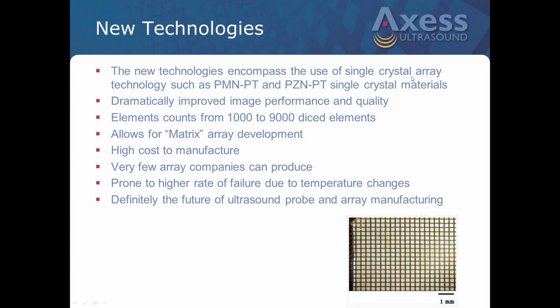Single crystal arrays are truly that. It's an absolute single piece. Think of it as a single piece of glass, crystal material, that's all one. And essentially the entire array is firing. I'll get into this a little bit more, but there's a lot of electronic control over single crystal arrays. What it means is a single crystal versus individual elements. Now, one of the things single crystal does, and I am a firm believer, and I've seen many images with various manufacturers' probes, is a dramatic improvement in image quality. The performance is very, very good with single crystal materials.